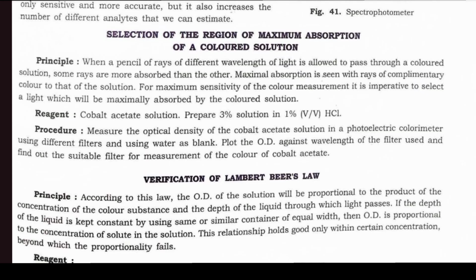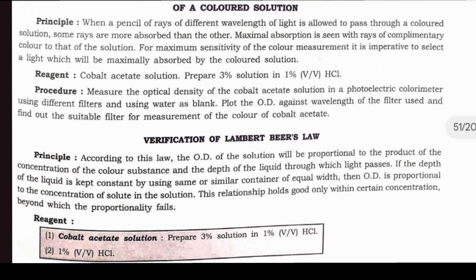Reagent: cobalt acetate solution. Prepare a 3% solution in 1% volume by volume HCl. Procedure: measure the optical density of the cobalt acetate solution in a photoelectric colorimeter using different filters and using water as blank. Plot the OD against wavelengths of the filter used and find out the suitable filter for measurement of the color of the cobalt acetate.